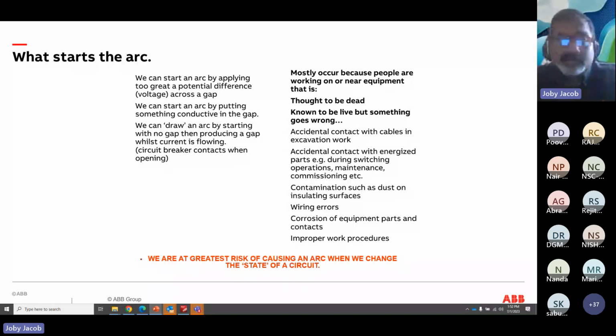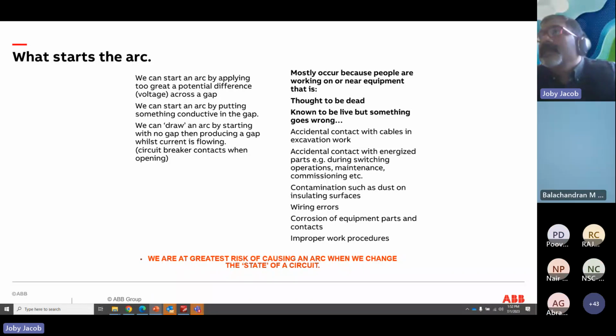The other things include physical failures resulting from dust and not properly maintaining the equipment. If it gets too much dust, it reduces the current carrying capacity and the heat propagating capacity of the conductor itself. During testing and commissioning, it can happen due to wiring issues, aging, corrosion of the equipment and parts, and lack of proper work procedures. These are some of the things that can create and start an arc.